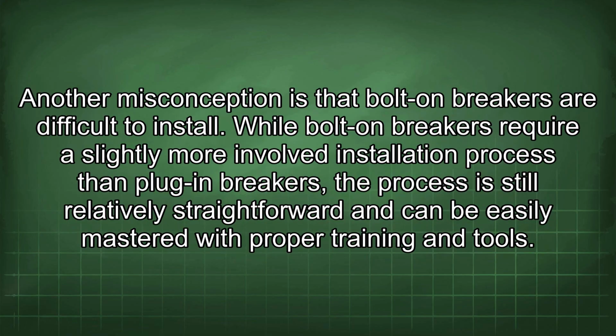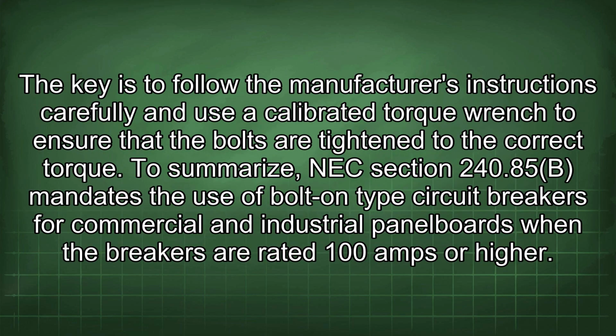Another misconception is that bolt-on breakers are difficult to install. While bolt-on breakers require a slightly more involved installation process than plug-in breakers, the process is still relatively straightforward and can be easily mastered with proper training and tools. The key is to follow the manufacturer's instructions carefully and use a calibrated torque wrench to ensure that the bolts are tightened to the correct torque.